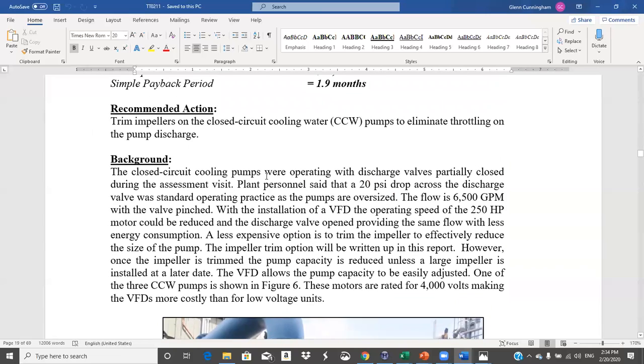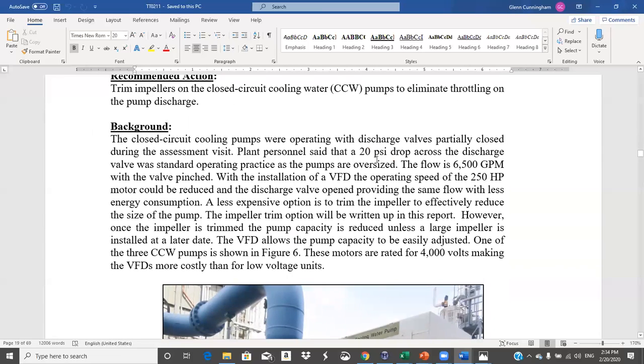Background, let me see. The valve was pinched. Oh, I know. I remember now. They had pressure gauges on either side of the valve. And what they did, this pump was too big. It caused problems if they didn't close this valve on it. So they would close the valve until they measured a 20 PSI drop across the valve. Okay, so 20 at 6,500 GPM. So roughly, you can calculate that.